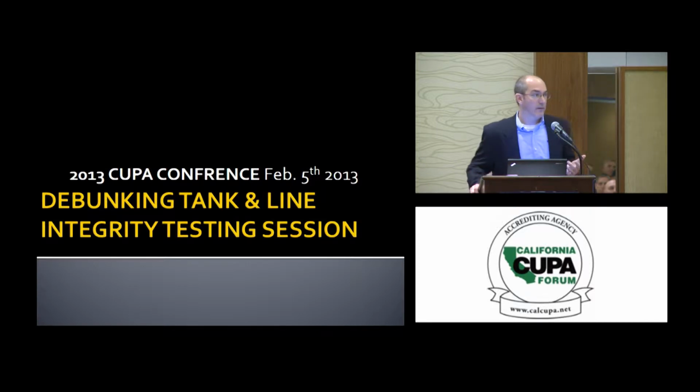I'll give just a brief theory of the volumetric tank testing. This is what I call the classical volumetric test, where you measure level and temperature. Steve, I believe, is going to talk about the Alert testing, which gives a quantitative result in a different way. But the volumetric test applies to our Sure Test method and a number of other methods that try to measure the level of the fuel and then the temperature of the fuel and then calculate a leak rate. It's fairly simple in a way, but there's a lot of math and algorithms in it.